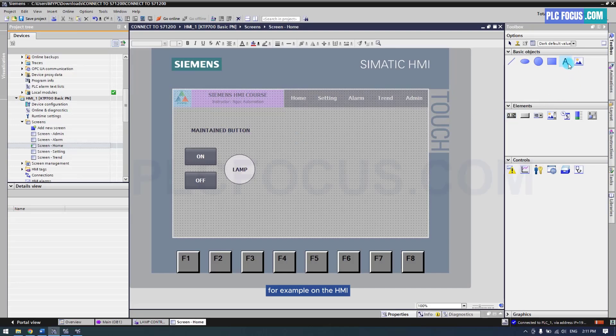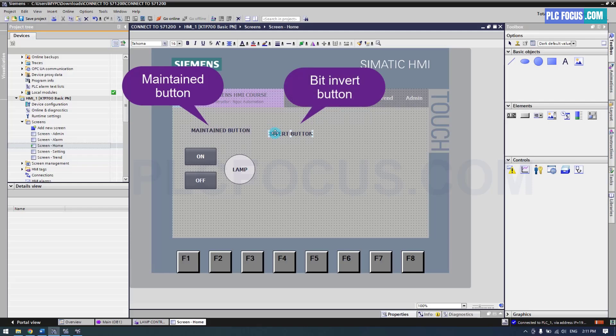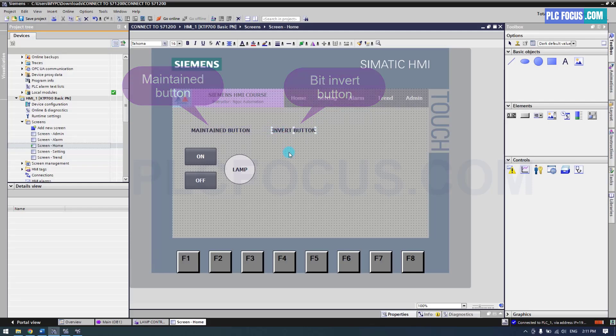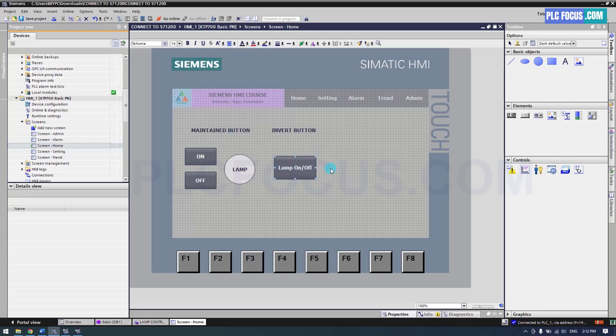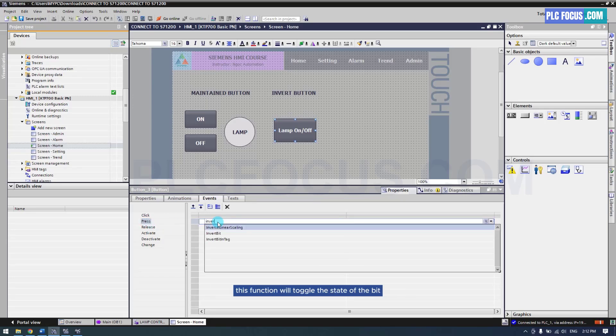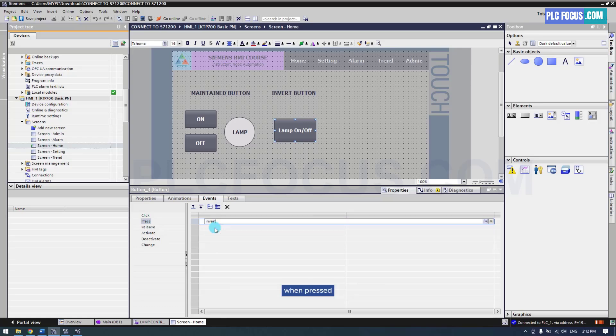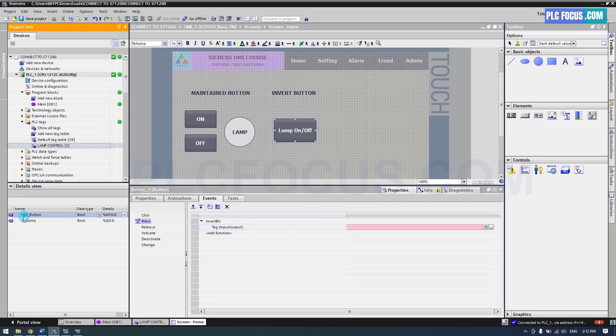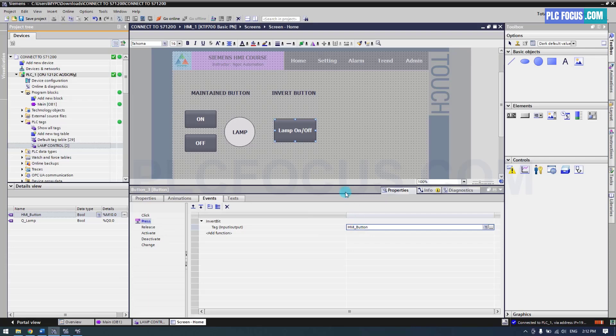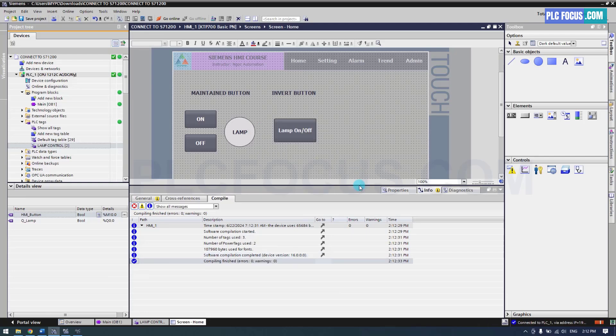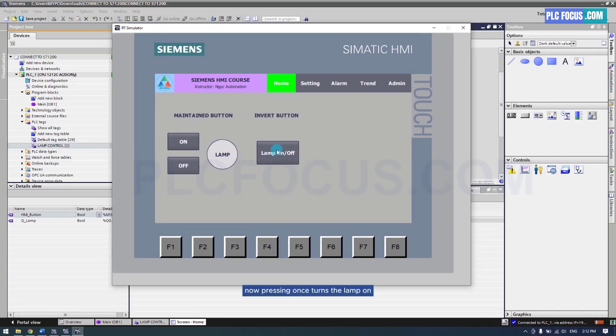For example, on the HMI you create a toggle bit button and name it Lamp On or Off. Under the press property, find the invert bit function. This function will toggle the state of the bit when pressed. Now pressing once turns the lamp on, and pressing again turns it off. This is the toggle bit button.